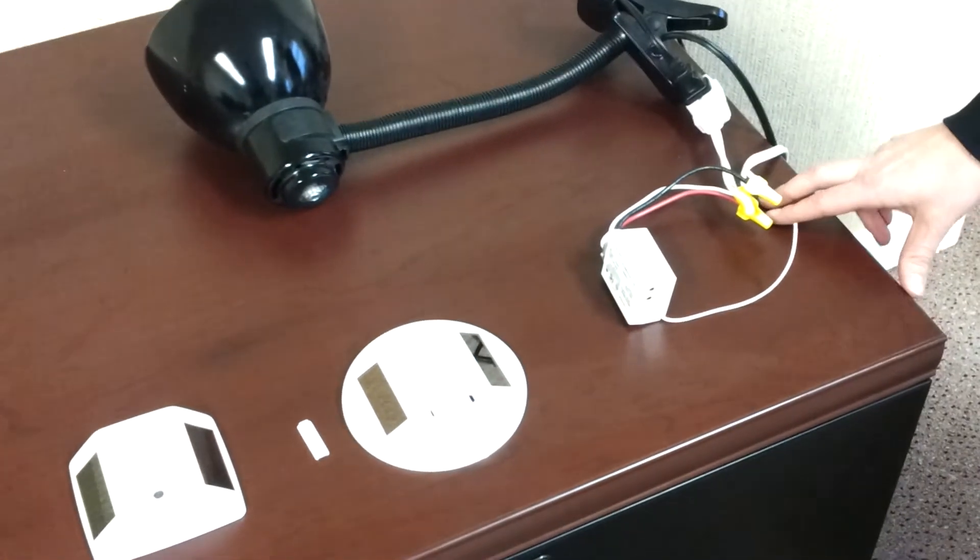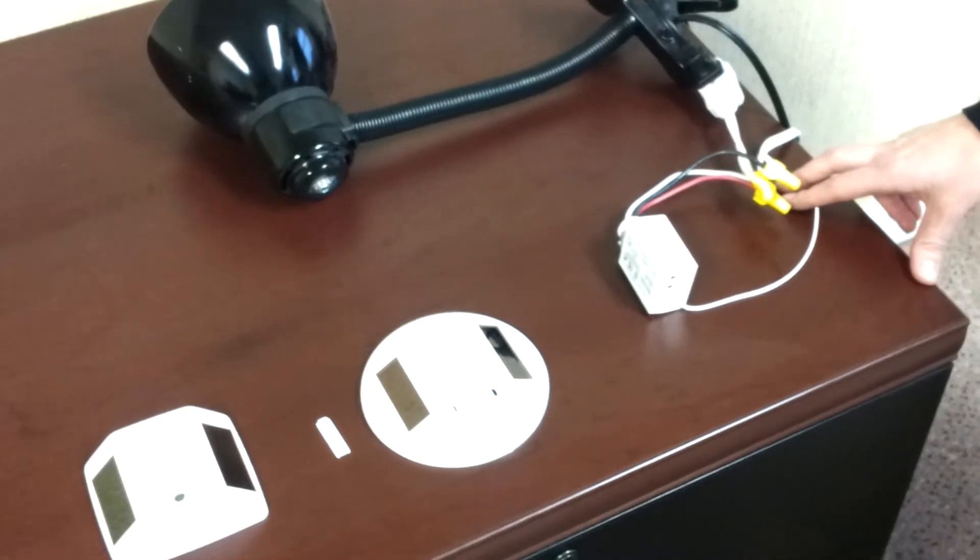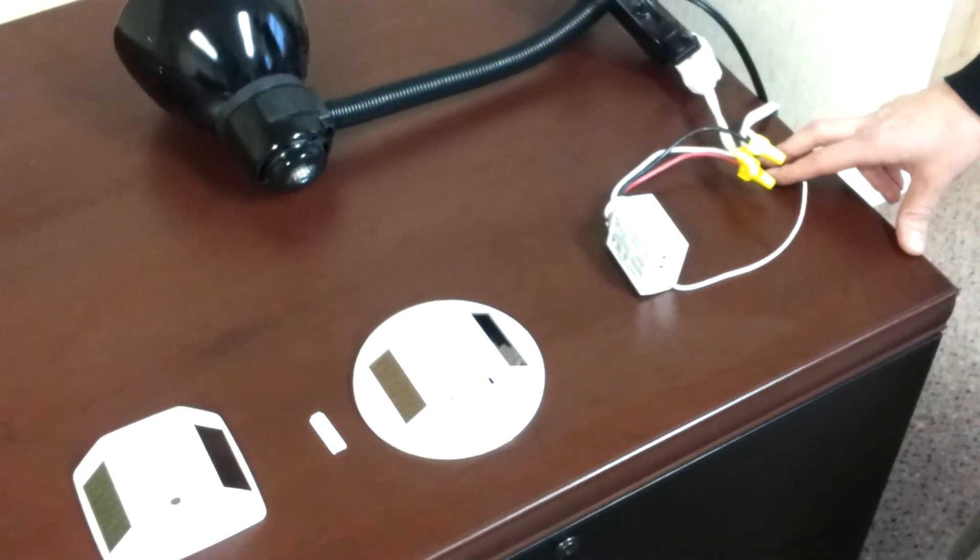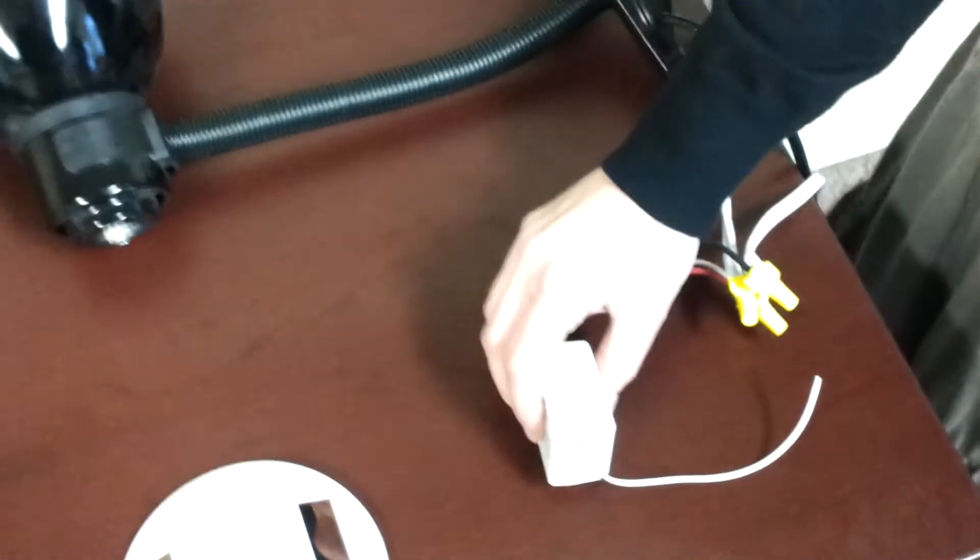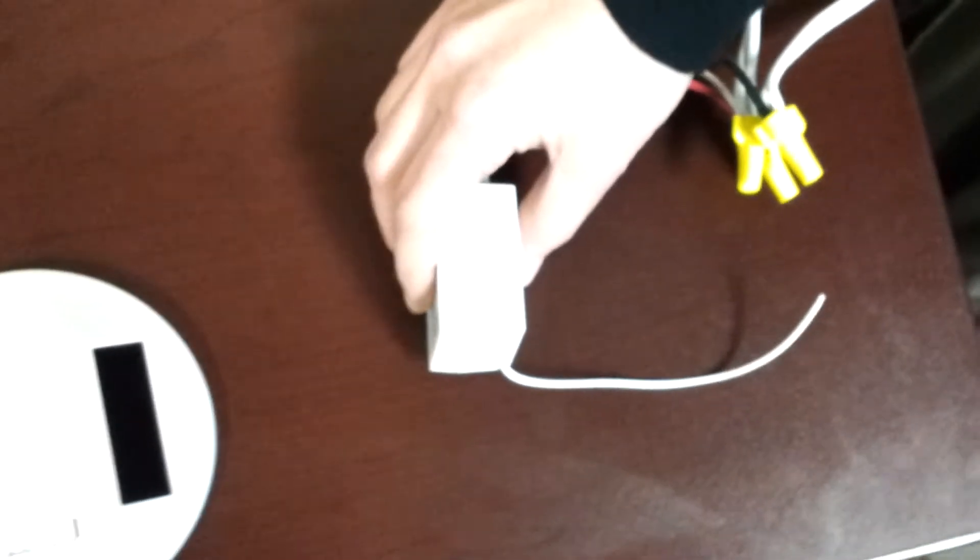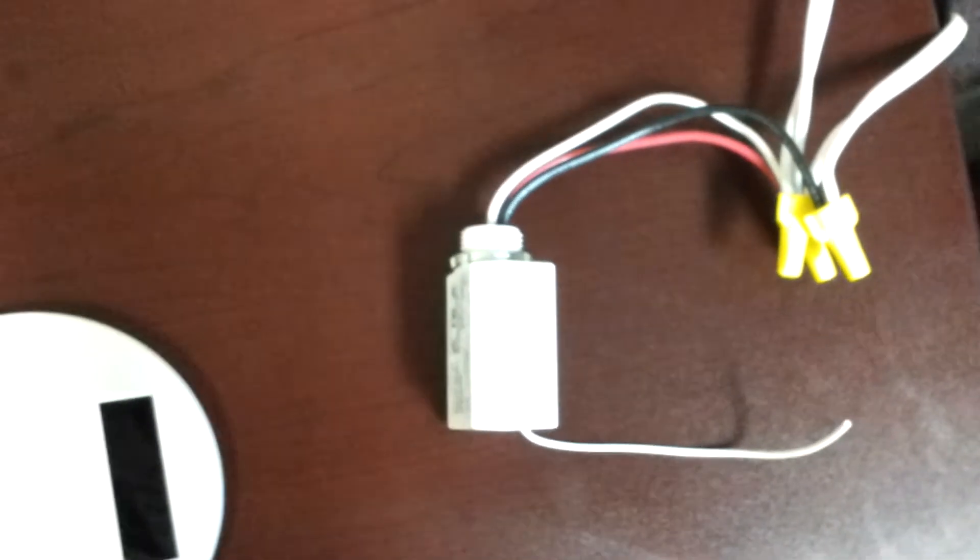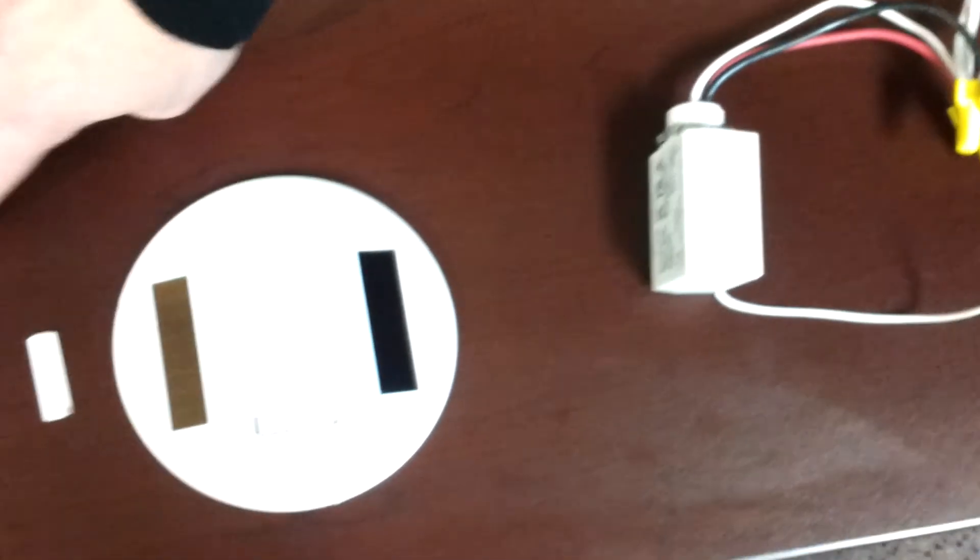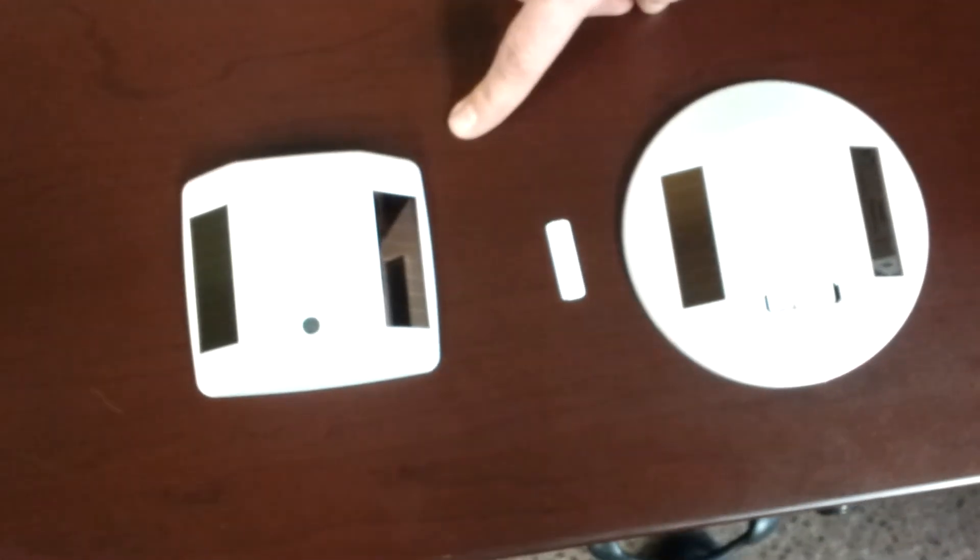Connect the wire and relay based on instructions in the installation guide. The relay supports various learn modes for configuring certain functionality. For this application, we'll use learn mode 1 for the light sensor with a double press of the teach button to give the light sensor priority and hold lights off when they're not needed.